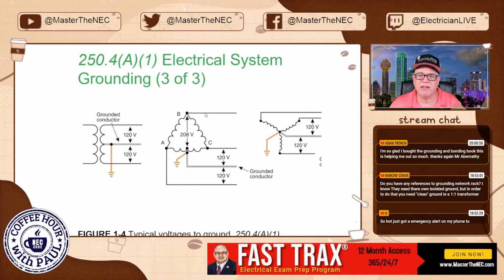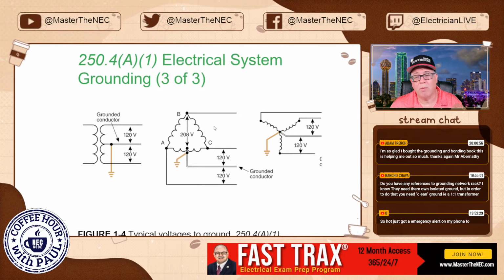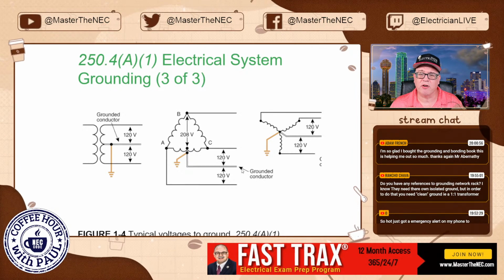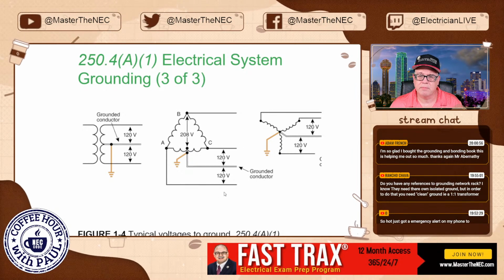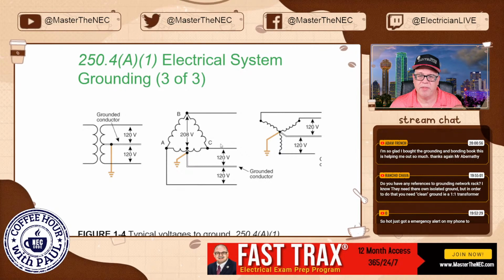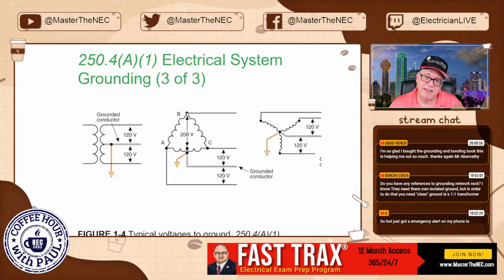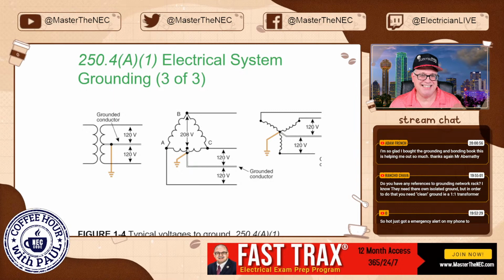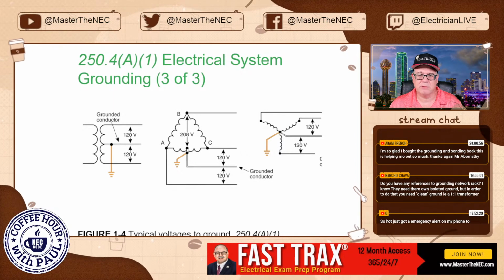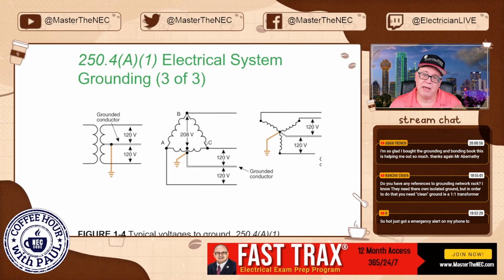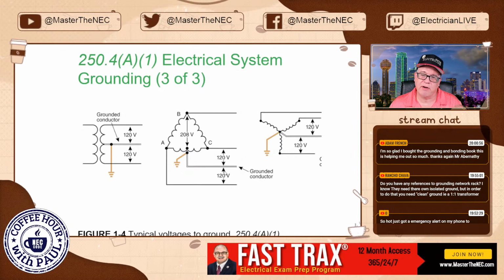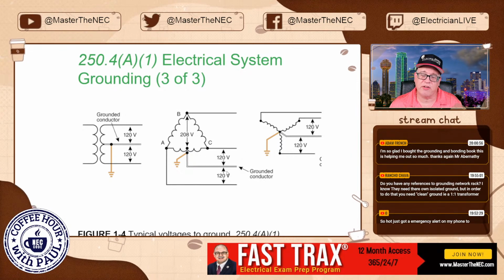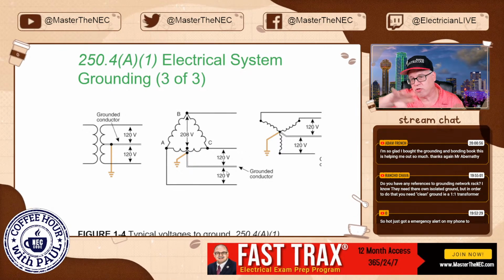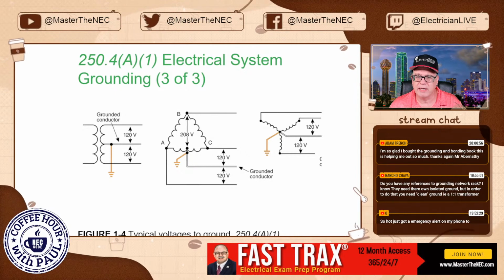Any one of these, all right? Well, take that back. This is still a grounded conductor on this system. Okay, on this system. Because, yeah, if I make this connection here to here, then no, it's not. But any of the others, phase to ground, phase to grounded. So this is a grounded. This is typically what you're going to drop if it was a drop down off to your utility.